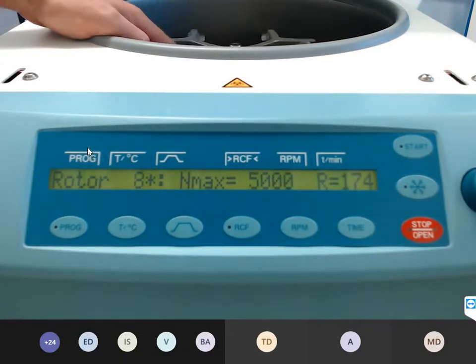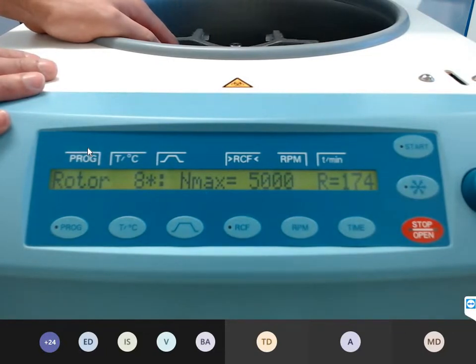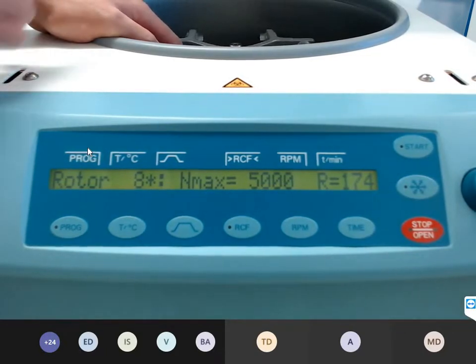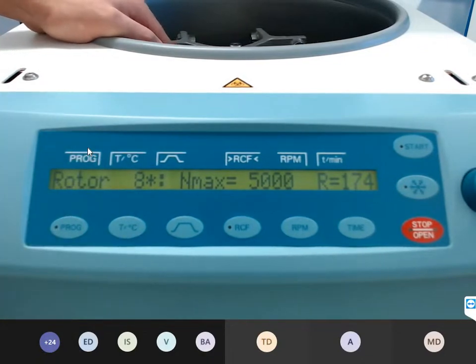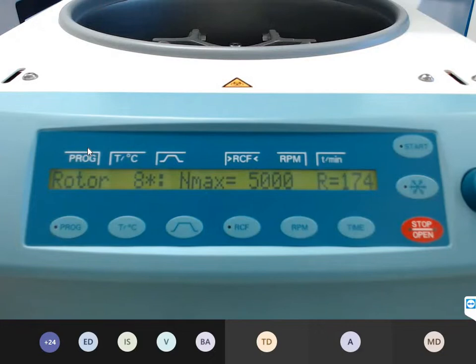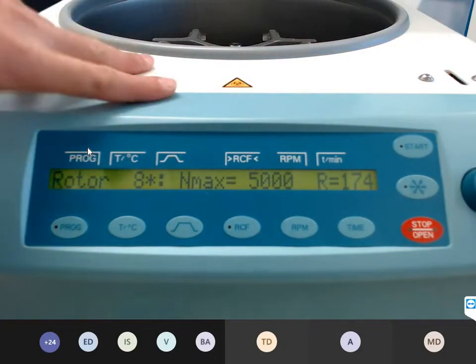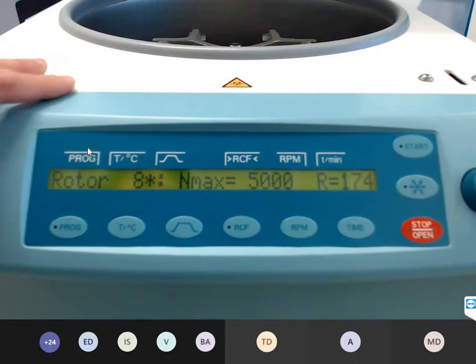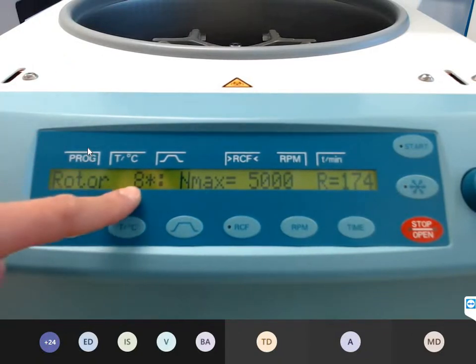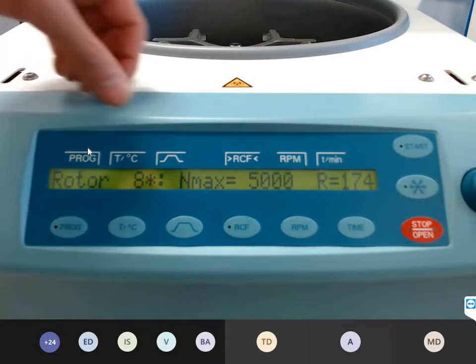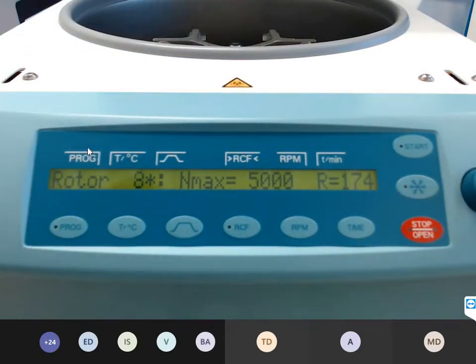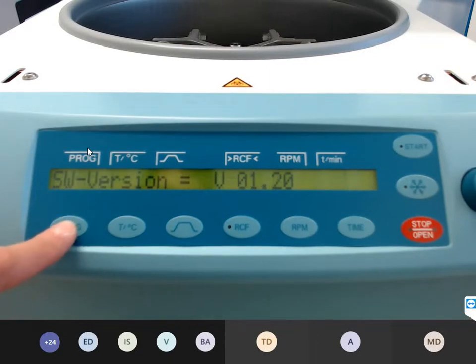We have also here on this device the tacho sensor for the recognizing of the tacho code, because we can use here different rotors, and this device reads also automatically the tacho rotor code, and then knows the maximum RPM and also the radius. Software version, the version of the frequency converter.